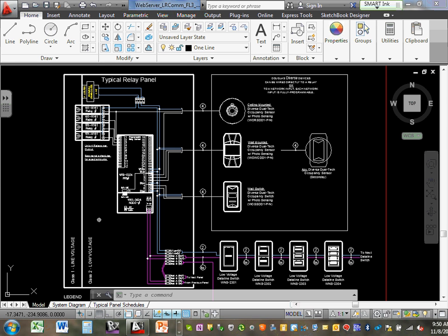But I don't want to switch the whole thing together, so then we have hot switch drops, line voltage, that give me some functionality, but a lot more home runs, right? And a lot more circuit breakers. What it really does is let me take that same single circuit breaker and break that one breaker down into multiple loads. So if you think of the relay as just another switch, I've got a switch that's back there, and then I'm just turning that switch on and off with a local switch. Okay, does that make sense?